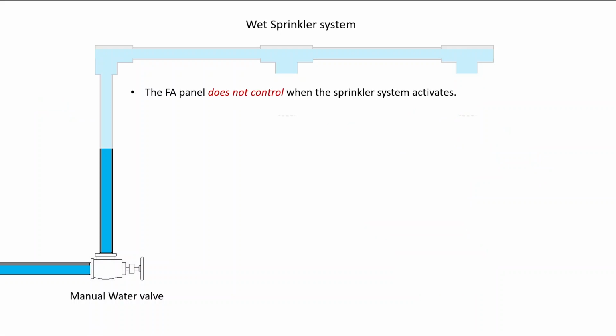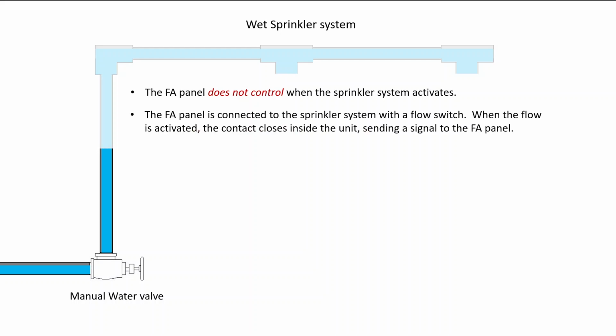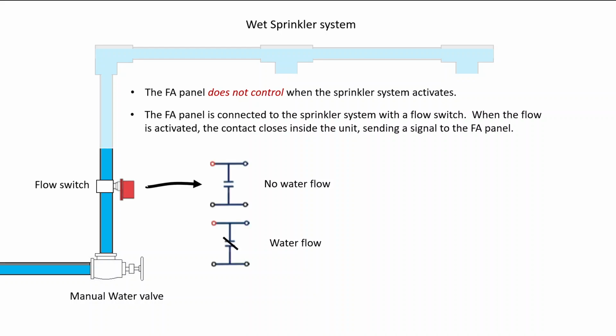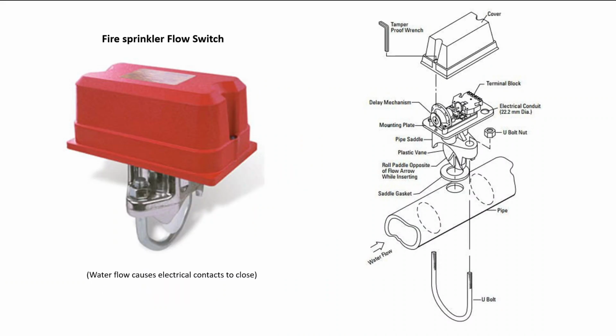It's important to understand that throughout this procedure, the fire alarm panel did not control when the sprinkler system activated. The fire alarm panel is connected to the sprinkler system with a flow switch. When the flow is activated, the contact closes inside the unit, sending a signal to the fire alarm panel. So we can see here a set of contacts in there, no flow and water flow, and we'll see that it's connected much the same as how a standard pull station would be connected back to a fire alarm panel. This is what a standard fire sprinkler flow switch looks like.